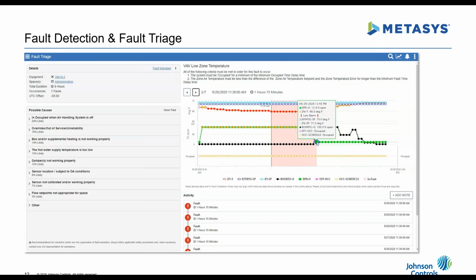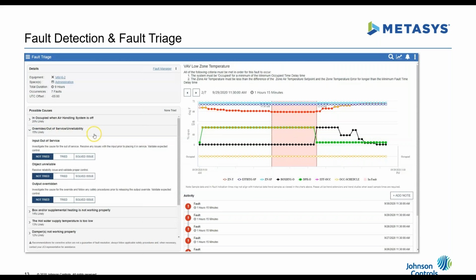Now that I'm clear somebody has overridden this, I can go to the possible causes, open up overrides, out of service, and unreliable. Looking at the last option, output overridden, it says to investigate the cause for the override and follow any safety procedures prior to releasing the output override, and validate expected control.